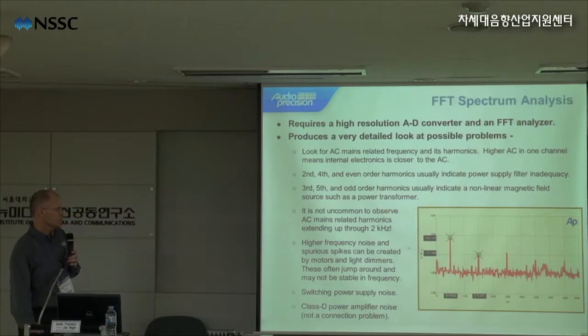It's not uncommon to observe AC mains related harmonics extending up through 2 kilohertz in frequency. Higher frequency noise and spurious spikes can be created by motors and light dimmers, and these often jump around in the spectrum and they may not be stable with frequency. There's also switching power supply noise and Class D power amplifier noise. That's not a connection problem, it's just a problem in general.